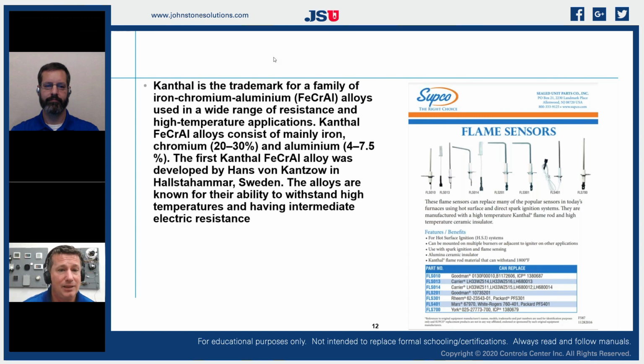So we take a Kanthal rod and insulate it with a little piece of ceramic, put it on a standard steel plate, and then attach a screw so that we can anchor it. But in most manufacturing processes, it is simply a piece of Kanthal steel, a ceramic insulator, and a plate, which is why they're typically only a few dollars. They're not very expensive. They can withstand up to 1800 degrees Fahrenheit of direct contact.